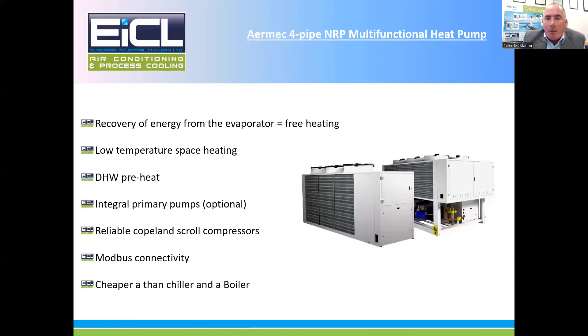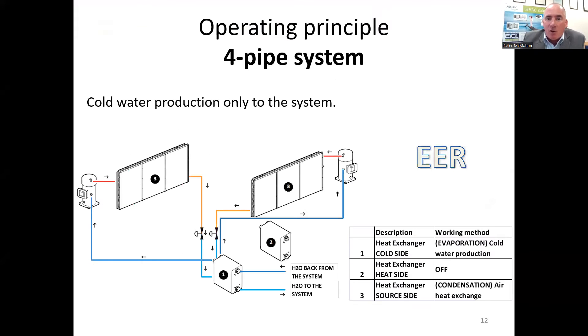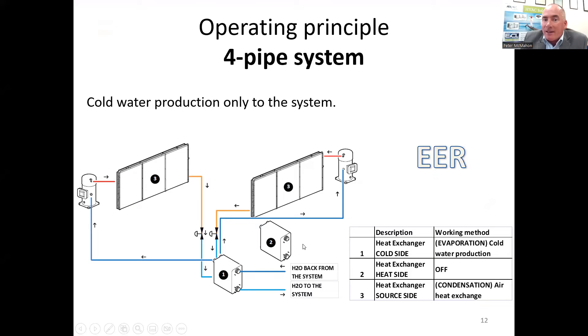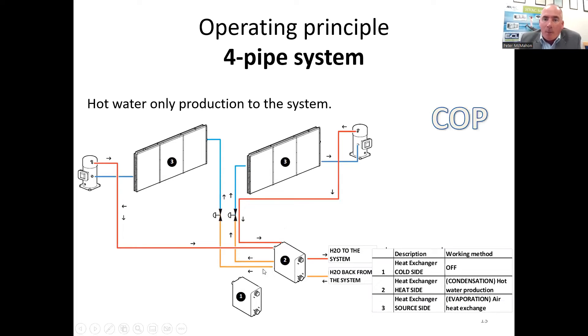There are three modes of operation. The first is cooling only, where all your circuits are dedicated to providing cooling only. You can see there are two heat exchangers — one for cooling and one for heating — and the heating is not being used when acting in cooling mode. So basically it's acting like a chiller, plain and simple.